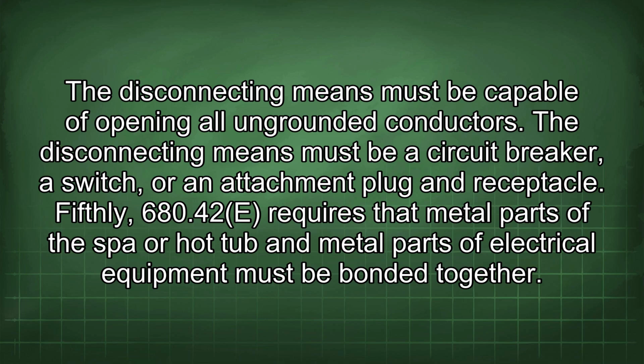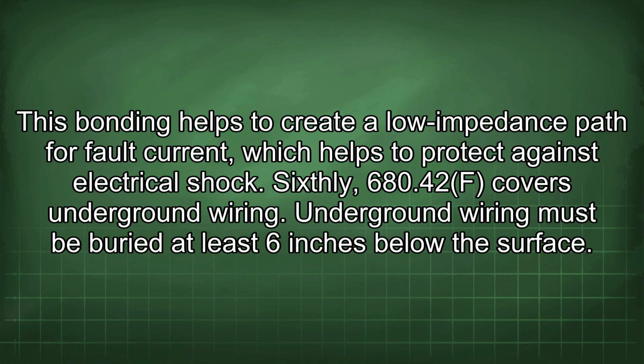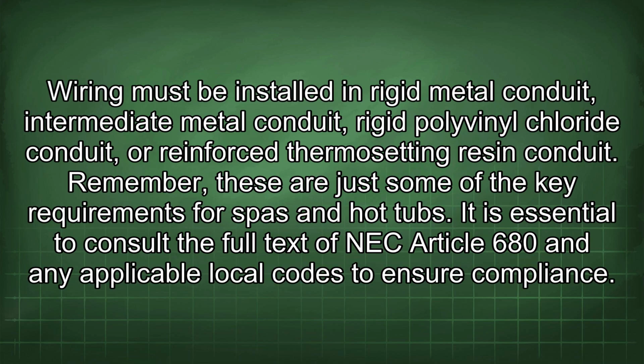Fifthly, 680.42(E) requires that metal parts of the spa or hot tub and metal parts of electrical equipment must be bonded together. This bonding helps to create a low impedance path for fault current, which helps to protect against electrical shock. Sixthly, 680.42(F) covers underground wiring. Underground wiring must be buried at least 6 inches below the surface. Wiring must be installed in rigid metal conduit, intermediate metal conduit, rigid polyvinyl chloride conduit, or reinforced thermosetting resin conduit.